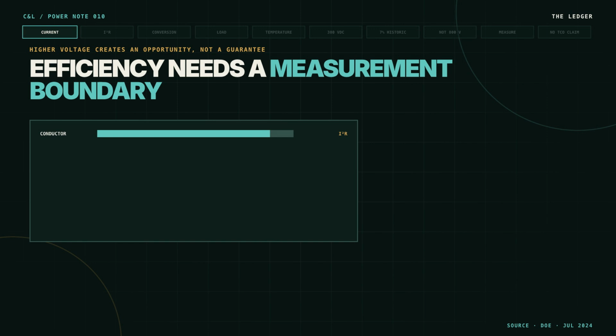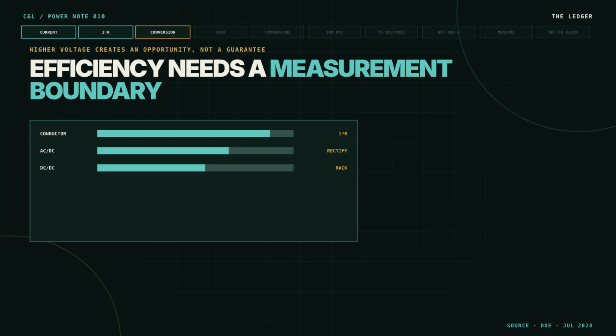Lower current can reduce conductor loss, and central conversion can remove repeated alternating current to direct current stages. But racks still need direct current conversion, protection, cooling, and redundancy. Their losses change with load and temperature.